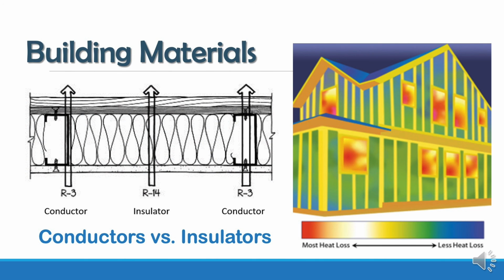So you might recognize that wall stud concept that we looked at last week of the framing. We also see the top of the top plate and the bottom plate of some of these walls. And our least amount of heat loss is at the bottom of the first floor and up at the roof. That to me is indicating that there is insulation at the second story between the attic space and the ceiling of the second floor.